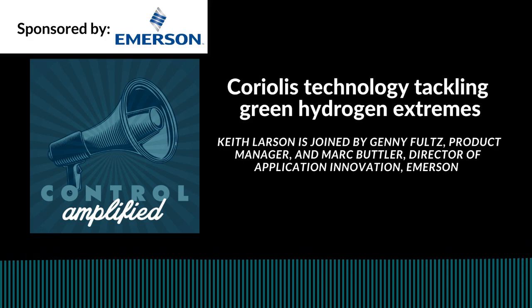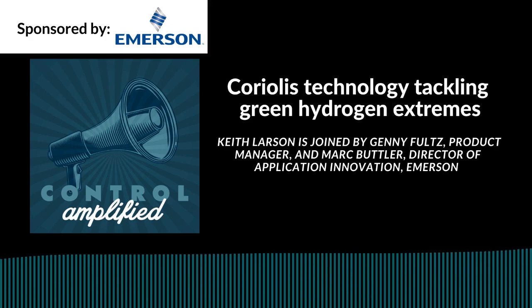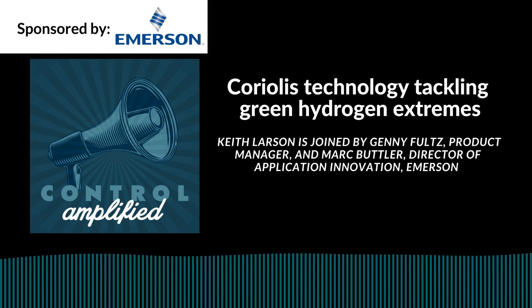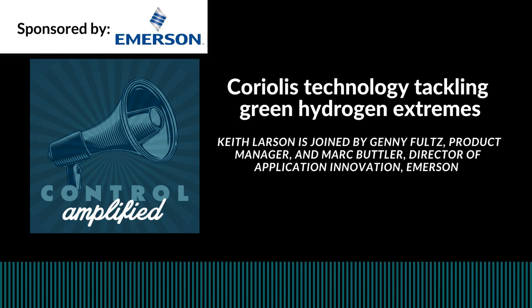Genny, what other sorts of in-plant applications is the HPC series appropriate for? And can we expect to see other extensions of the HPC line? HPC015 is a great high-pressure Coriolis sensor for chemical injection applications. We've also seen it used in paint applications that require high pressure. We have a line extension that has the C22 nickel alloy that would help cover those corrosive applications. But also, what we're seeing in the future is the need for a higher flow rate, higher pressure HPC sensor that can help deliver more of that high flow rate that's necessary for the hydrogen market. And everything is rapidly accelerating within that space, and we think that maybe in the future we might have opportunity to see more of these high pressure sensors, possibly for liquid hydrogen and some others.